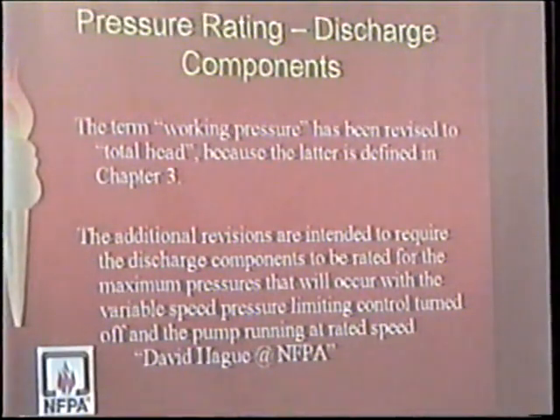Right. And this is what Dave was talking about before, that your system components have to be rated for the maximum discharge pressure, even if the variable speed controller is running at full speed. I took that off of one of the slides that Ed brought back from the seminar, so that's why I put David Hogg's name on there. Gotta be kosher when you do this stuff.